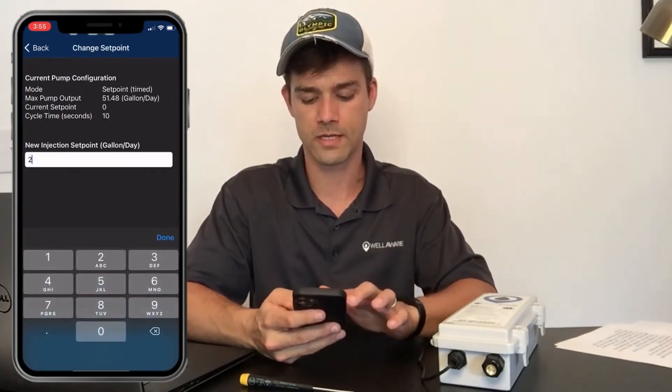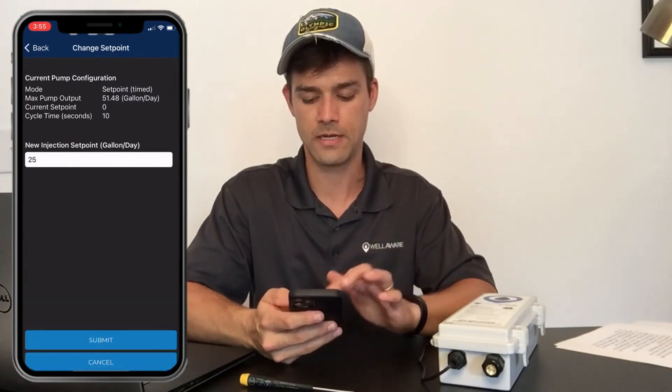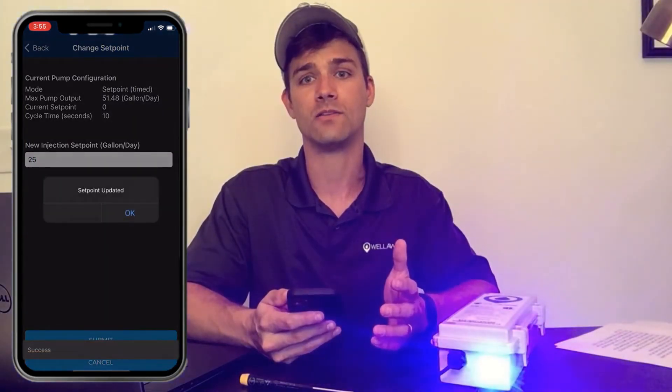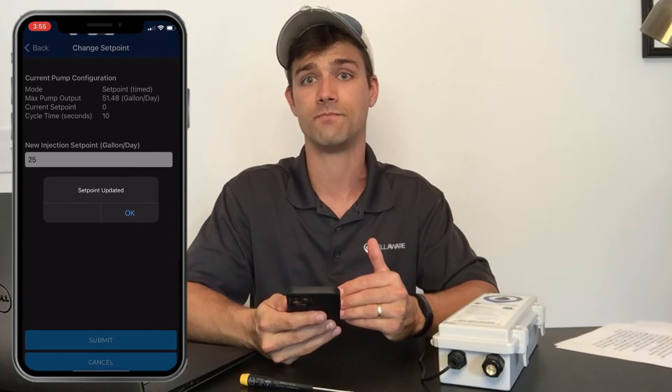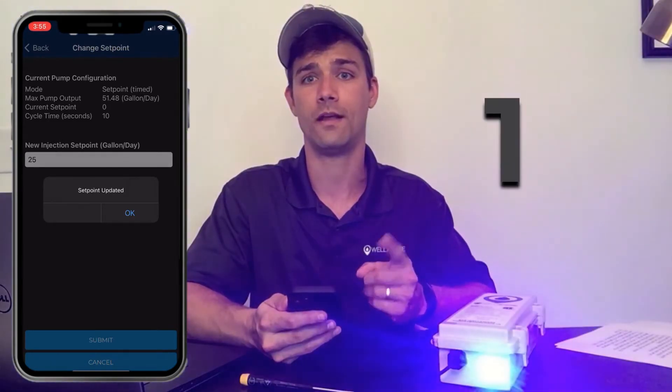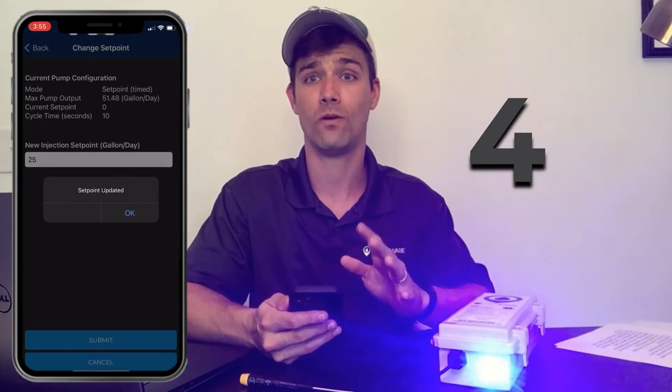The pump has a maximum output of about 50 gallons per day, and the cycle time is set to 10 seconds. I'll set the set point to 25 gallons per day — about half of max output — so we'd expect a 50% duty cycle. I click 'change set point,' set it to 25 gallons per day, and hit Submit. The LED comes on, and it goes on for five seconds and off for five seconds — one, two, three, four, five — exactly as expected.